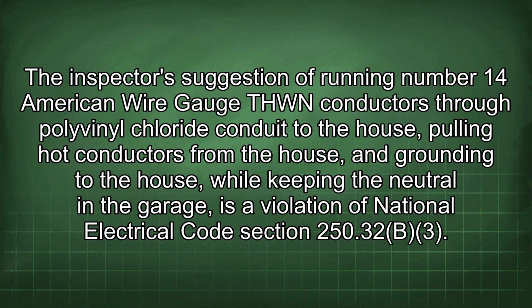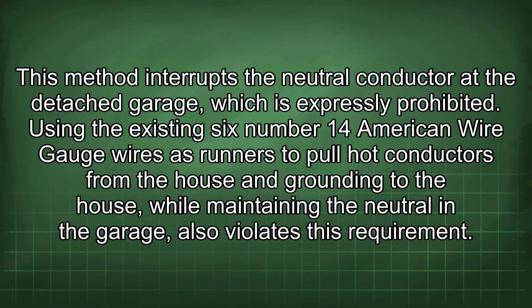The inspector's suggestion of running number 14 American wire gauge THWN conductors through polyvinyl chloride conduit to the house, pulling hot conductors from the house and grounding to the house, while keeping the neutral in the garage, is a violation of National Electrical Code Section 250.32(B)(3). This method interrupts the neutral conductor at the detached garage, which is expressly prohibited. Using the existing 6 number 14 American wire gauge wires as runners to pull hot conductors from the house and grounding to the house, while maintaining the neutral in the garage, also violates this requirement.